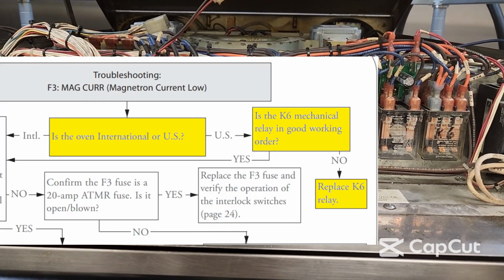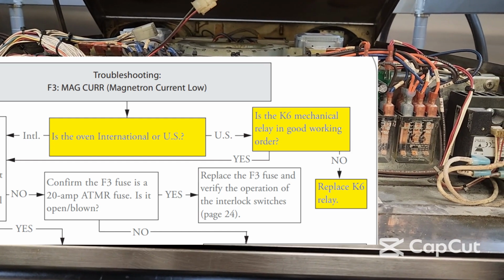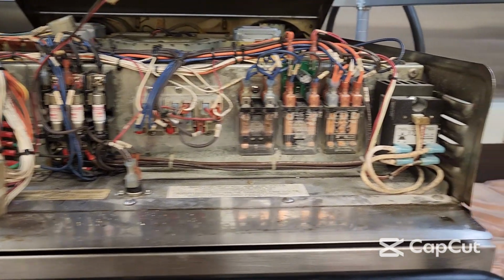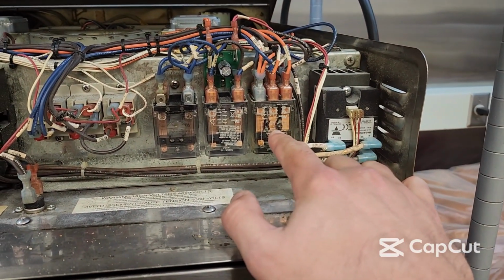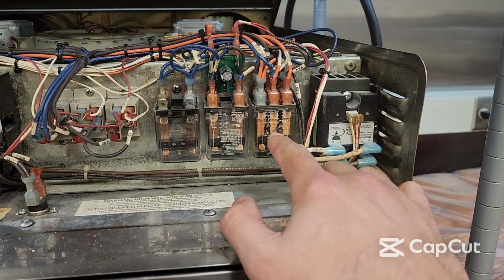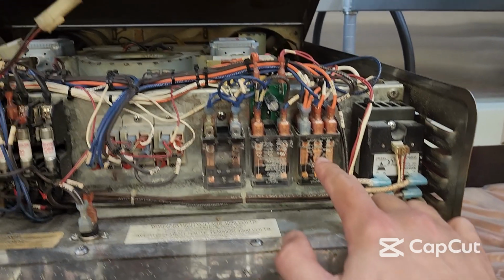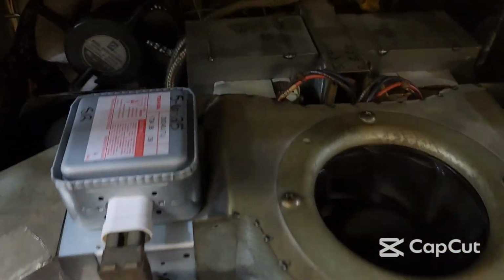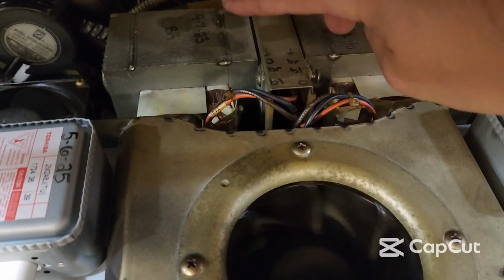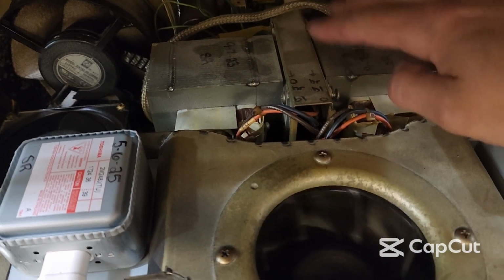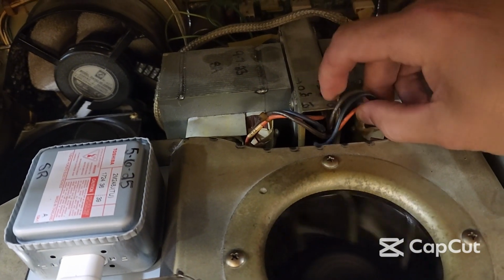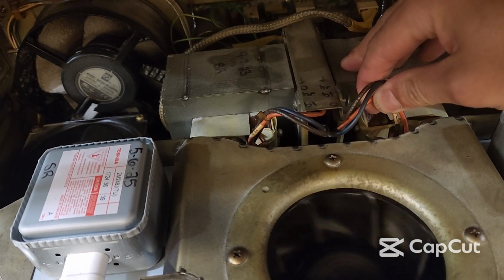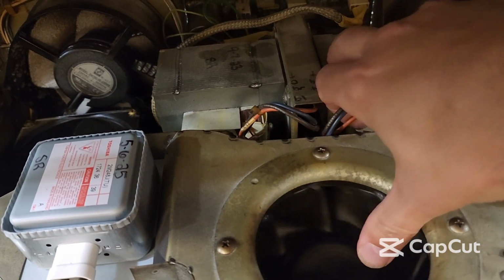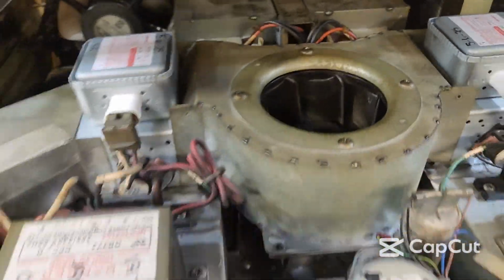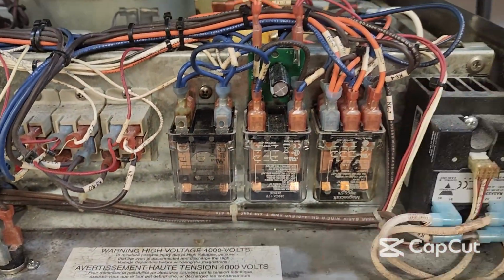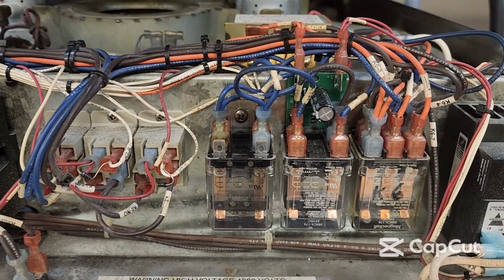We're in the US. And because this is a US oven, it has a feature that an international oven will not. And that feature is actually this K6. What this K6 does is it is basically switching the taps on the back of your transformers. So these transformers in the back here can be used for either 208 or 240 in the same transformer. So only when you look at these, you have 3 wires going to your primary side, and only 2 of those will be energized during normal operation.